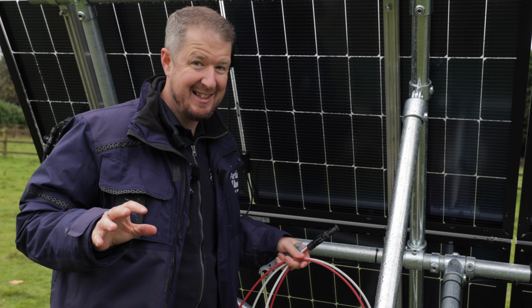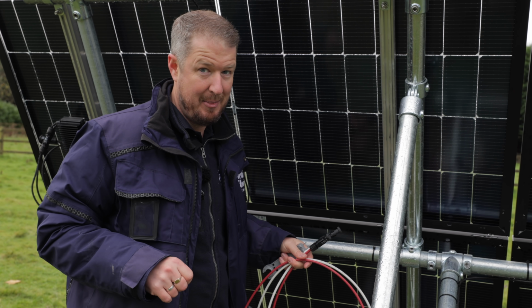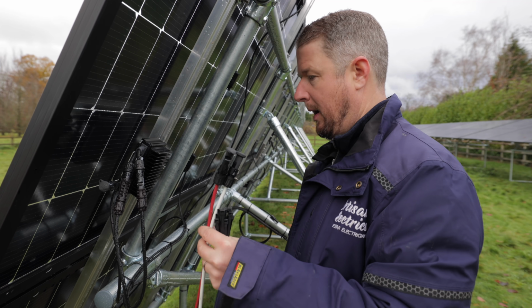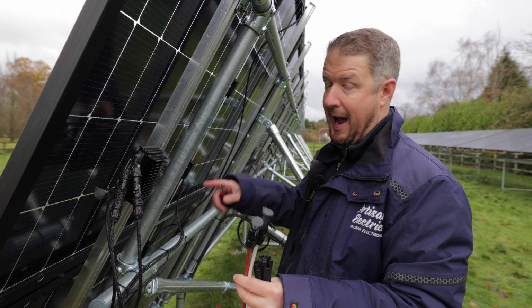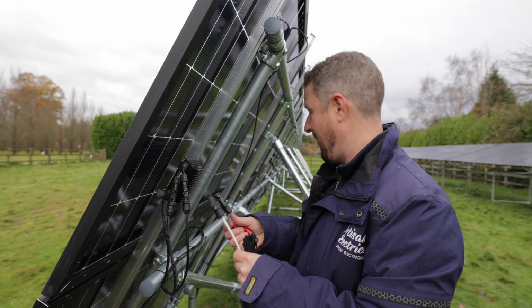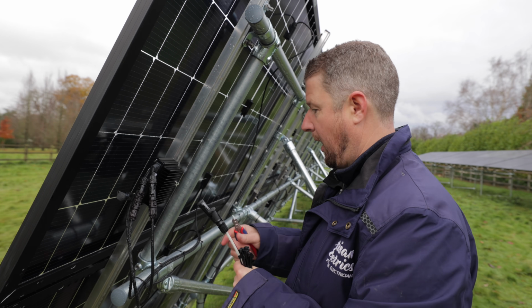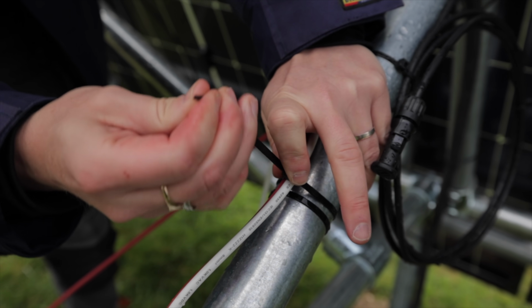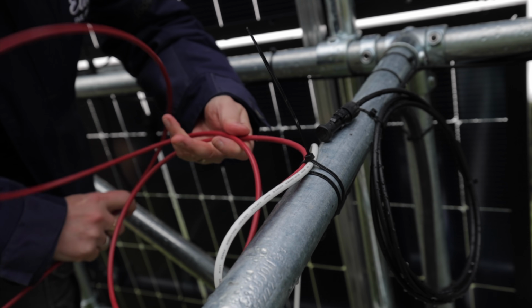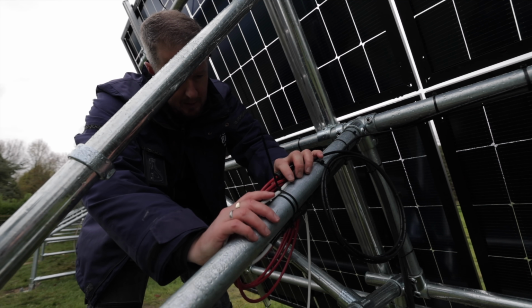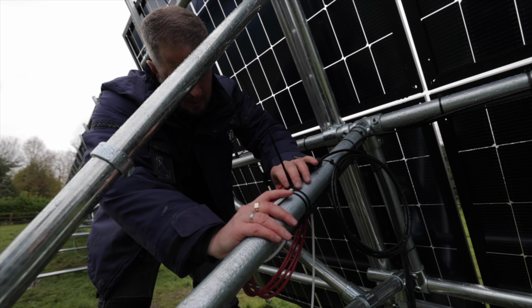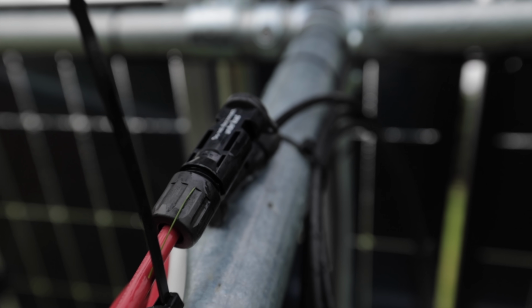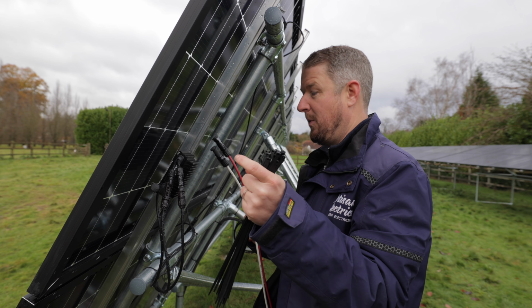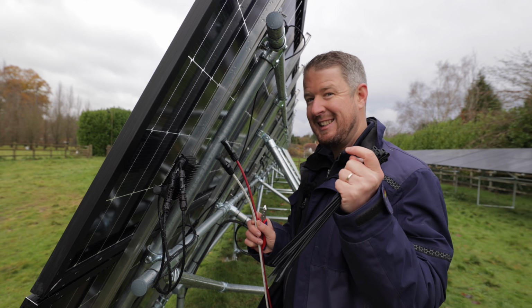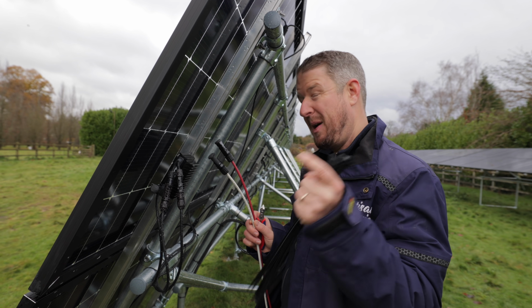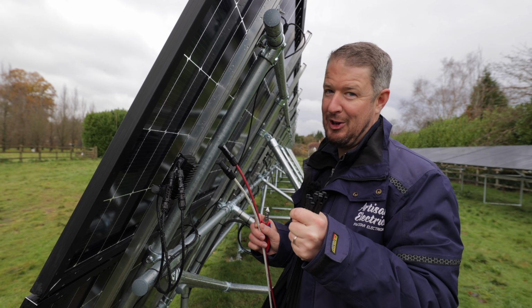Now we're getting to the stage where we can nearly start to connect everything up and liven it on. The final part is that we need to run the ends to their correct locations. This one's going to go in there, and the other one's going to go there, and then I'm going to cable tie them neatly. But I'm not going to connect them in until Ruben has finished doing the insulation resistance test, because if we insulation resistance tested it at the other end with the optimizers connected, we might have a problem - putting 1,000 volts through it is not a good idea.